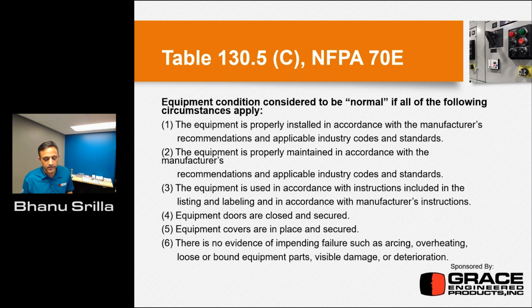A good example would be you can't use a low voltage system on a high voltage, or you can't use a low voltage Cat 3 duty test instrument on a Cat 4 application. This is what they're mentioning as used in accordance with the manufacturer guidelines. So there's this direct connection between how the equipment is installed and also how it's used, if you take the application context, and also what the manufacturer has designed this equipment for, okay?